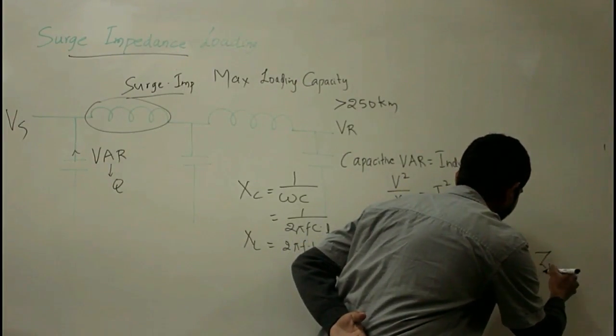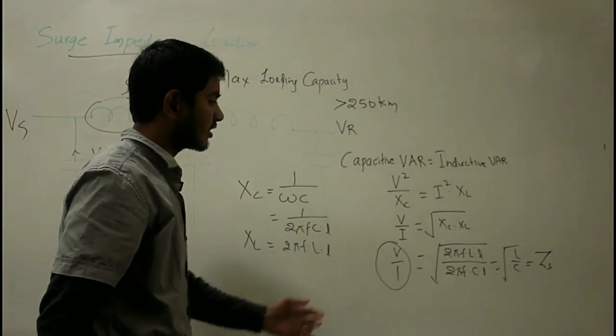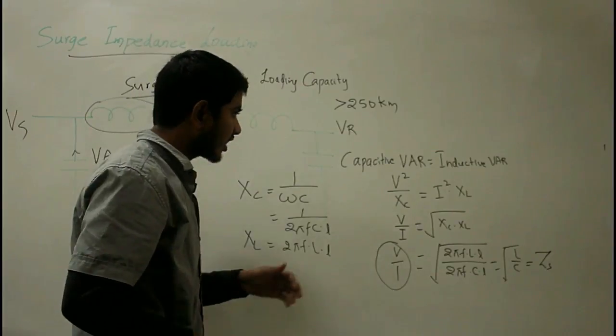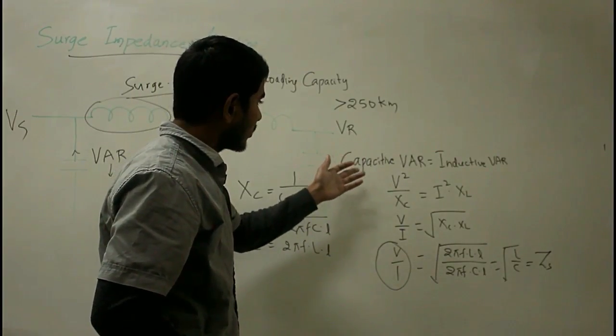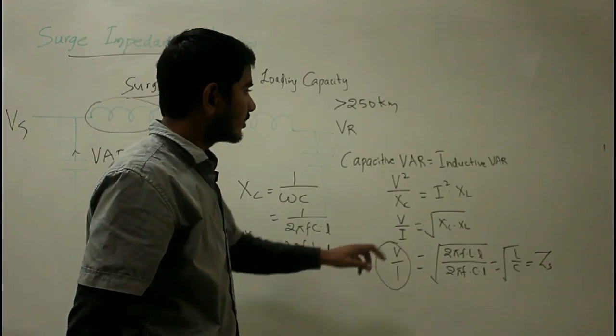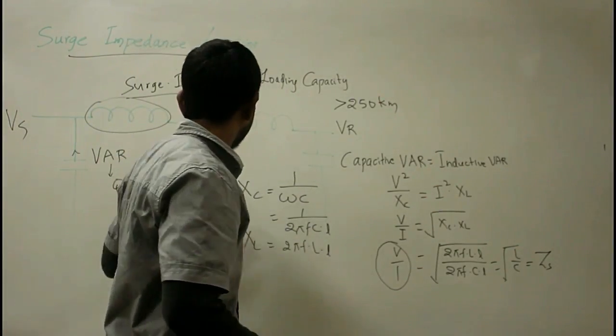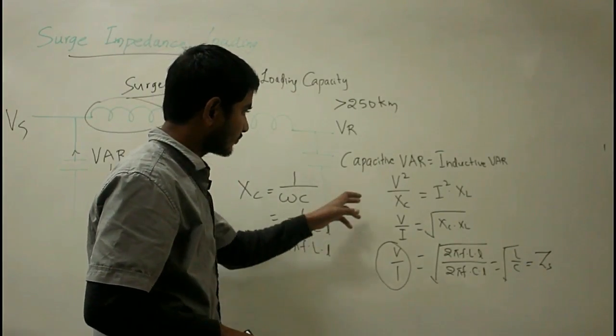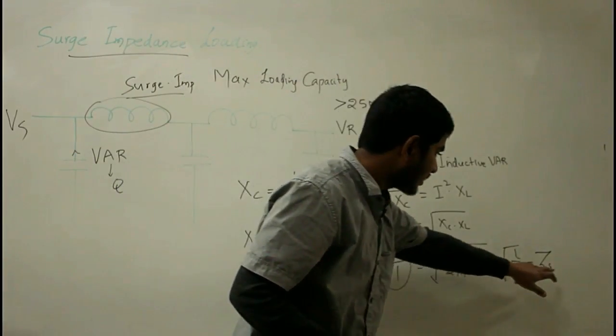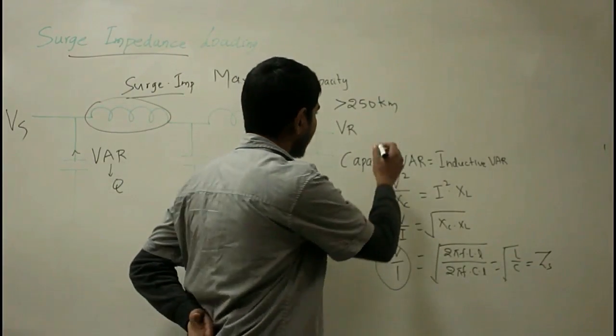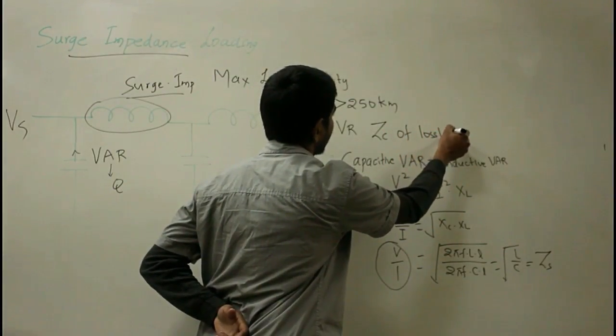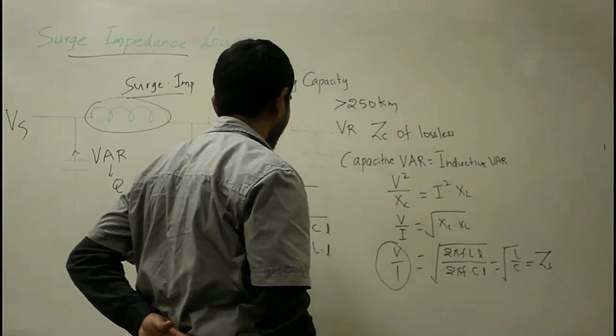When a purely resistive load is connected at the receiving end of the line equal to the surge impedance ZS, the capacitive VAR generated by the capacitor equals the reactive power consumed by the inductive component of the transmission line, making the line a lossless line. Therefore, surge impedance is nothing but the characteristic impedance of a lossless line.